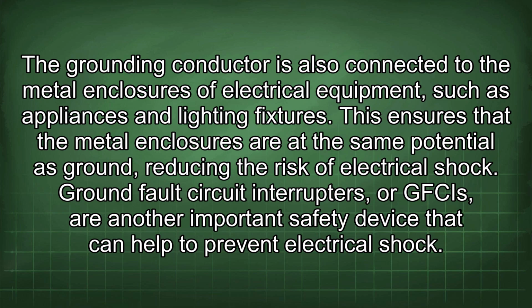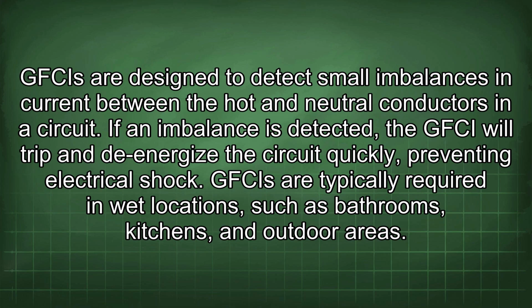Ground fault circuit interrupters, or GFCIs, are another important safety device that can help to prevent electrical shock. GFCIs are designed to detect small imbalances in current between the hot and neutral conductors in a circuit. If an imbalance is detected, the GFCI will trip and de-energize the circuit quickly, preventing electrical shock. GFCIs are typically required in wet locations such as bathrooms, kitchens, and outdoor areas.